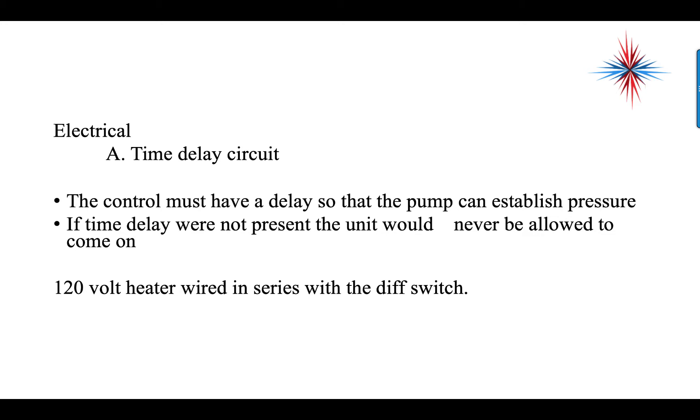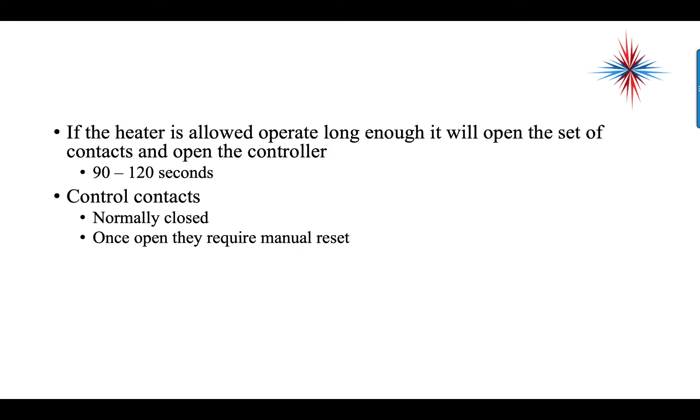We also use a 120-volt heater that is wired in series with the differential switch. If the heater is allowed to operate too long, it will use a bimetal contact to open a set of contacts and open the controller. This happens between 90 and 120 seconds after the heater is energized.